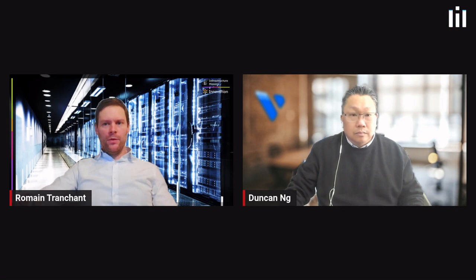At what point do you think liquid cooling will become mandatory? And also, do you think operators around the world are actually ready for what's coming, or even for the workloads of today? So definitely, if you're looking to adopt these 135 kilowatt Grace Blackwell type infrastructure, liquid cooling is a must today. If you're not already talking to your customers who are looking to have these workloads, or if you're a data center customer looking to find space for this, it's a conversation you should be engaged heavily with your team on both sides already.